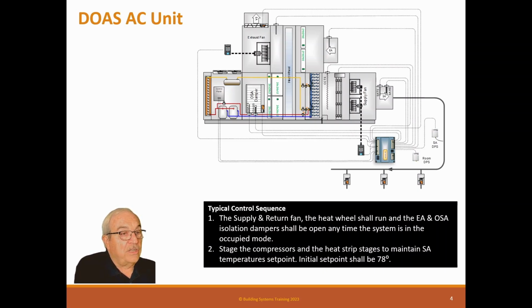Now, this is just like that unit we looked at before, that economizer deal we just looked at. But this one is bigger. It has an air conditioning circuit in, where the other one was just air and a heat exchanger. Stage the compressor and the heat strip stages to maintain supply air temperature set point. Initially the set point should be 78 degrees.